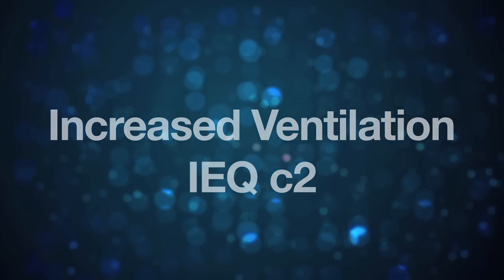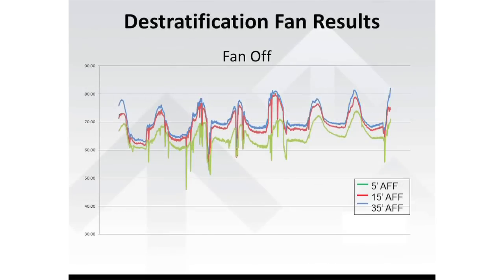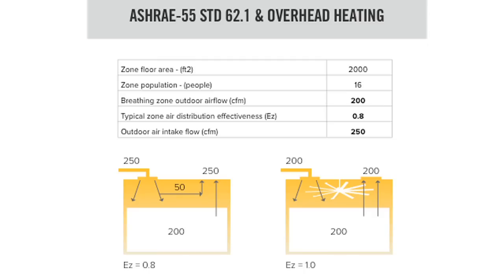HVLS fans can help in achieving increased ventilation in a space by helping to mix the air. When performing calculations for the outdoor air intake flow per ASHRAE Standard 62.1, there is a factor for zone air distribution effectiveness. This factor accounts for how good of a job the HVAC system does at getting the outdoor air into the breathing zone where the people are. If the system provides a well-mixed space, then less outdoor air intake is required. However, if there is stratification of the air, as is common with overhead distribution systems, then more outdoor air intake flow would be required.